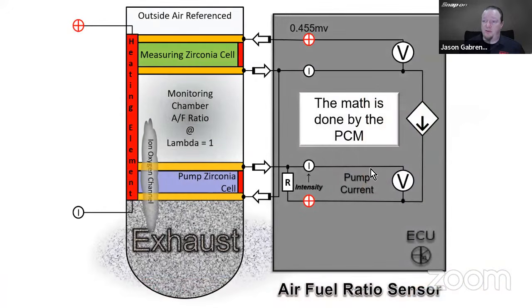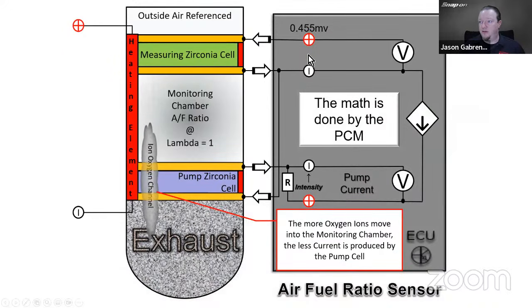So here's an example. It's moving the ions in and out between the chamber, and it's reading this voltage. By doing that, it causes the current to go positive or negative depending on what it happens to be. The more oxygen ions that move into the monitoring chamber, the less current is produced by the pump cell. So I guess the lower reading goes in.